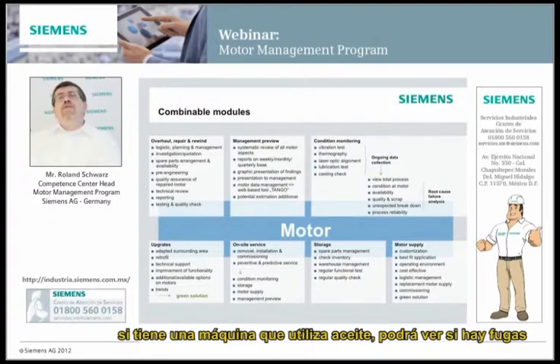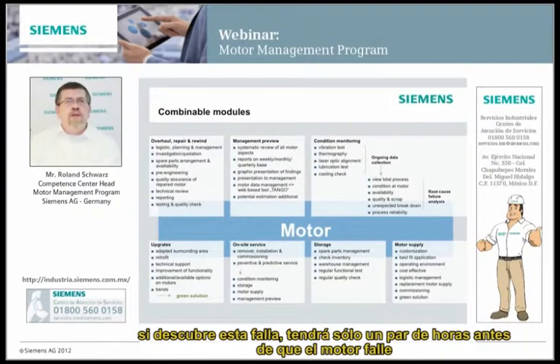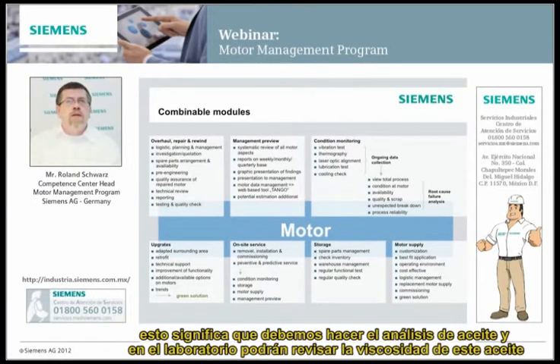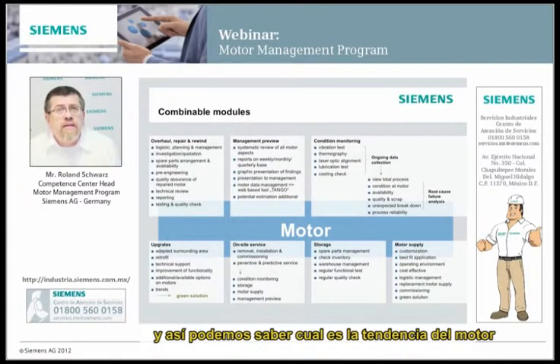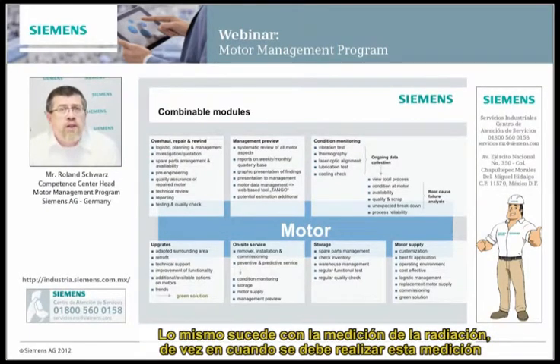For example, you have sleeve bearings with oil running. With visual inspection you can see if the oil is running out. If you find the oil running out, you may have only 2 hours before the motor breaks down. So we have to take care with oil analysis - when we get the results back from the laboratory, we can see the viscosity of the oil, and then we can determine the trend of the motor. Same with insulation measurement.